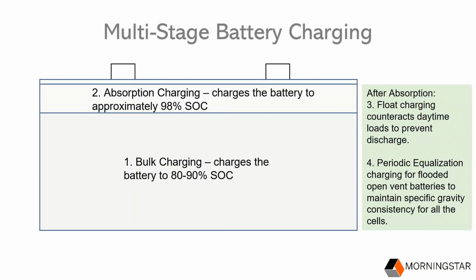This graphic illustrates the Morningstar controller's multi-stage battery charging process. The first stage is bulk charging, delivering 100% of available solar power to bring the battery up to a state of charge of approximately 80 to 90%. When the battery reaches the absorption voltage set point, constant voltage regulation is applied. This prevents heating and excessive battery gassing while the battery approaches a full state of charge. During the absorption stage, the charge current reduces as it requires less power to maintain the regulation voltage. When absorption charging is complete, the battery has about 98% state of charge. Then the charging current is reduced further, so the battery voltage drops down to the float voltage. And the float stage keeps the battery at maximum capacity throughout the day.